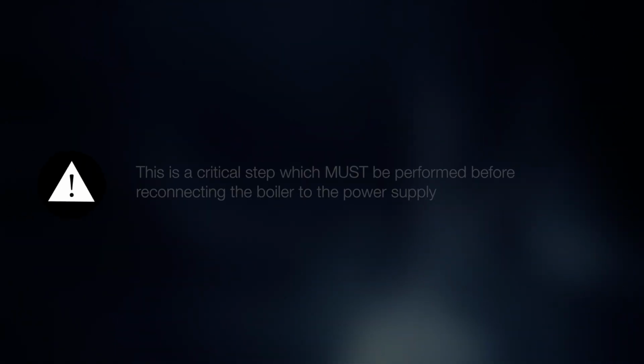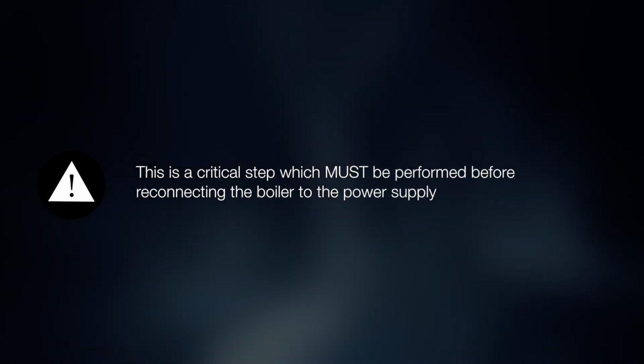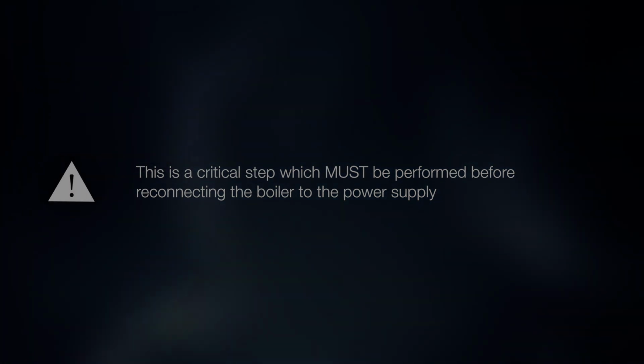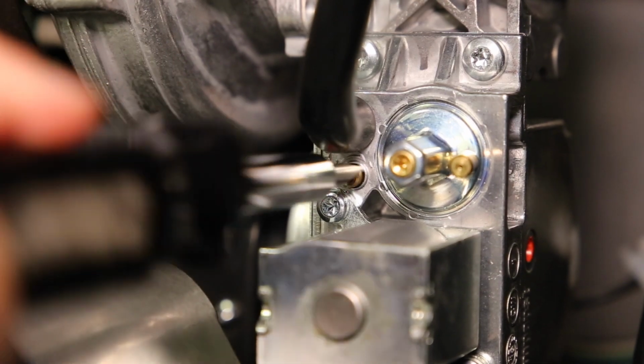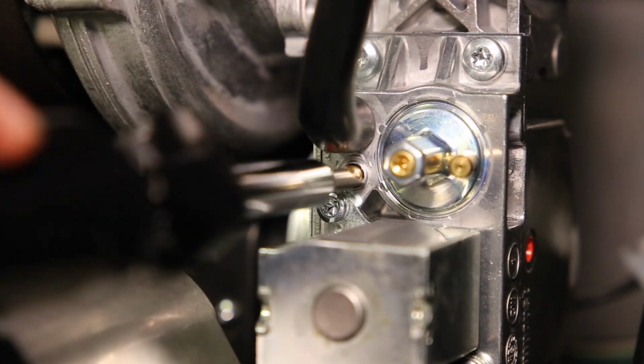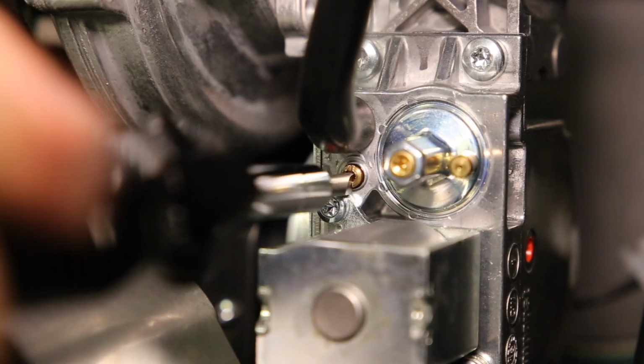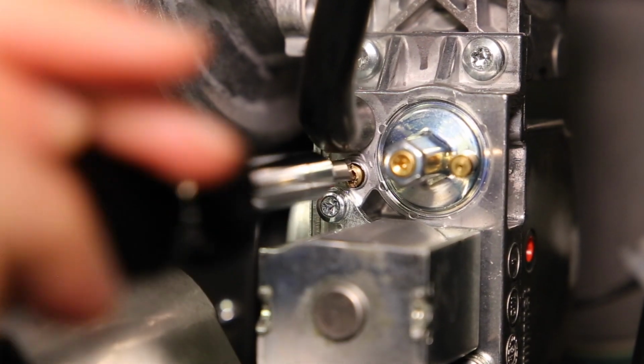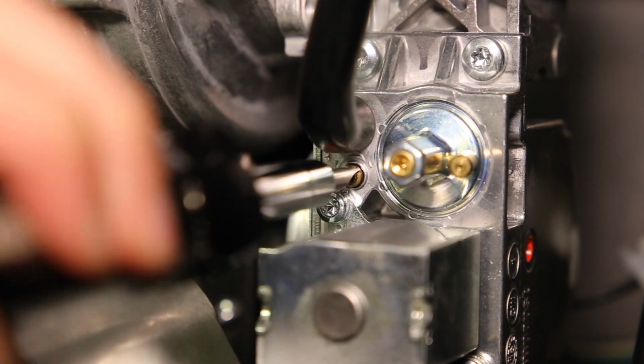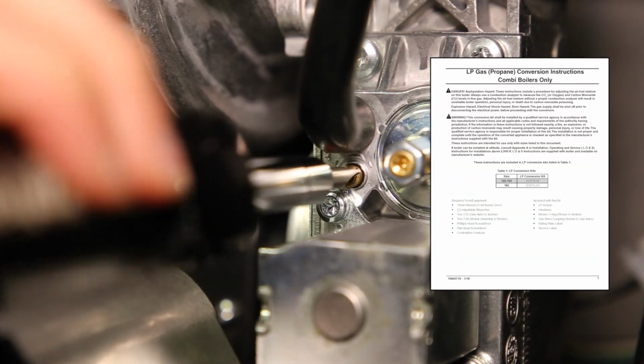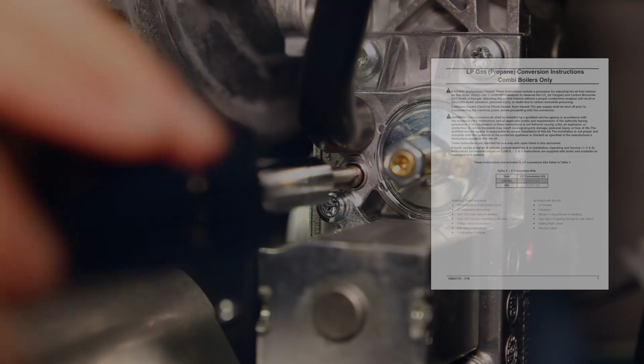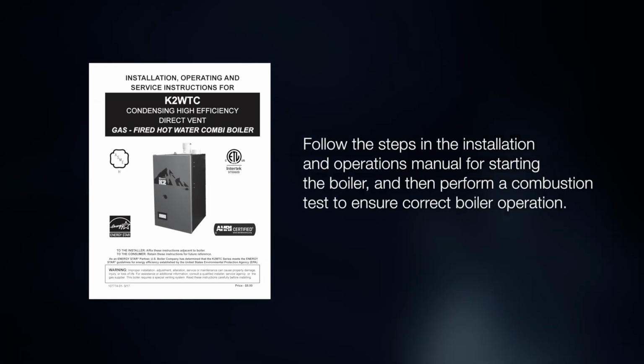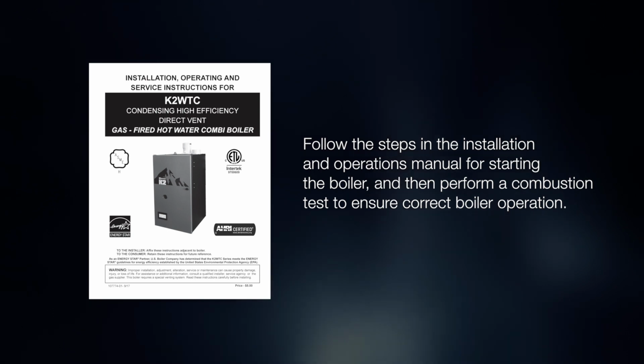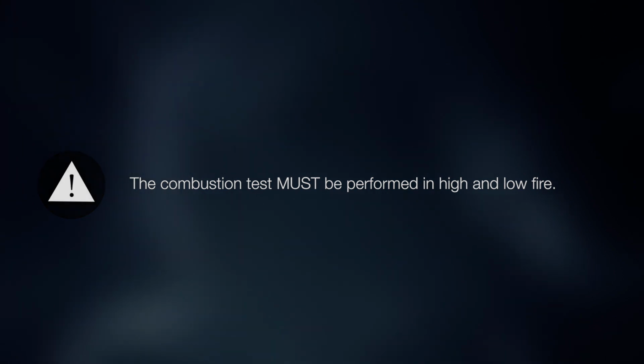Turn the gas supply to the boiler back on and check for leaks. This is a critical step which must be performed before reconnecting the boiler to the power supply. Before attempting to start the boiler, turn the throttle screw clockwise until it stops in the fully closed position. This should be several turns. Turn the throttle screw counterclockwise with the exact number of turns shown in the LP conversion kit instructions. The number of turns will depend on the boiler size. Follow the steps in the installation and operations manual for starting the boiler, and then perform a combustion test to ensure correct boiler operation. The test must be performed in high and low fire.